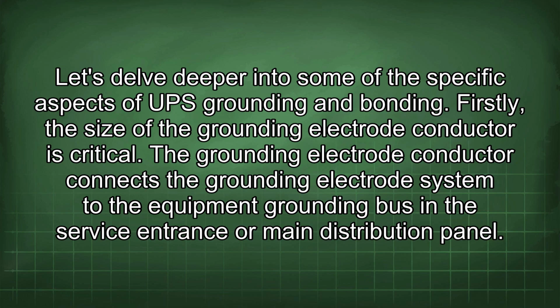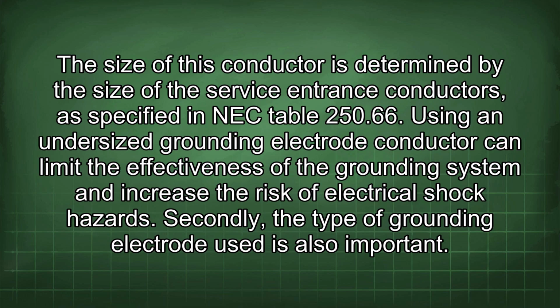Firstly, the size of the grounding electrode conductor is critical. The grounding electrode conductor connects the grounding electrode system to the equipment grounding bus in the service entrance or main distribution panel. The size of this conductor is determined by the size of the service entrance conductors, as specified in NEC Table 250.66. Using an undersized grounding electrode conductor can limit the effectiveness of the grounding system and increase the risk of electrical shock hazards.